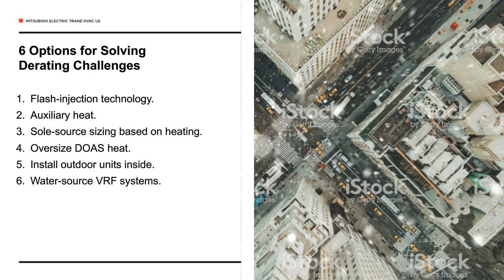We still have to follow the laws of thermodynamics as it gets colder out. Generally speaking, capacity and efficiency of heat pump systems, including VRF systems, drop. But we'll look at the specifics of that. And as shown on the screen here, here are some approaches that we've seen used. First one, flash injection technology. Second one is auxiliary heat. Then we'll talk about sole source sizing based on the heating load. And that's simply just oversizing, if you need to, your condensing unit such that you can meet the heating loads.